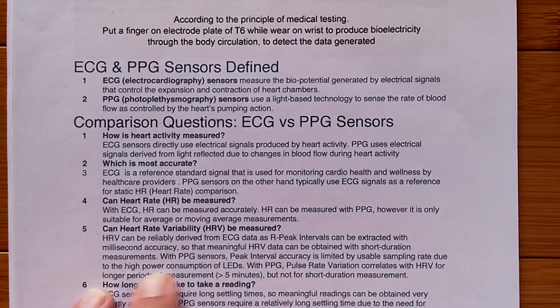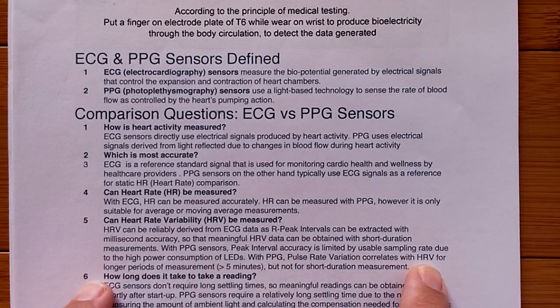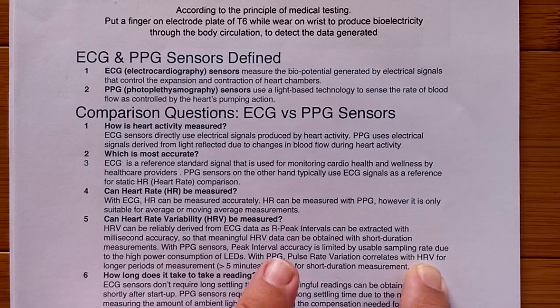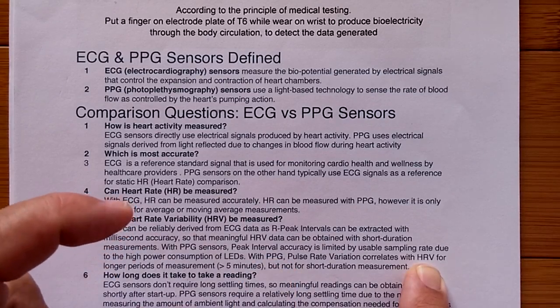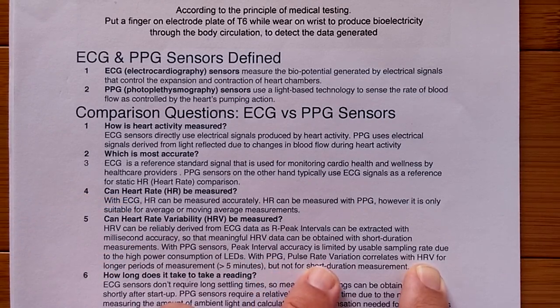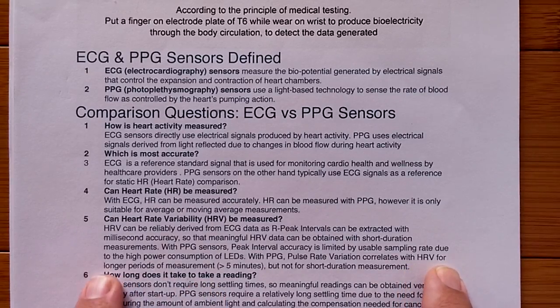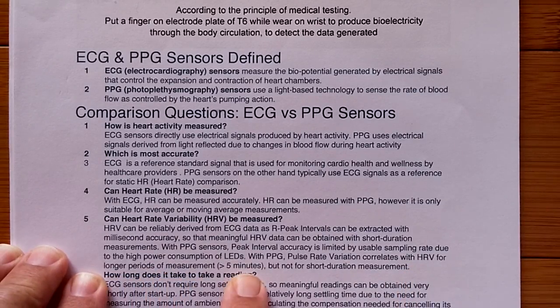With PPG sensors, peak interval accuracy is limited by usable sampling rate due to the high power consumption of the LEDs. With PPG, pulse rate variation correlates with HRV, right? With PPG, this is the light diode kind of thing, PRV, pulse rate variation, correlates with the heart rate variation for longer periods of measurement, over 5 minutes, but not for short duration measurements because it's doing a moving average.